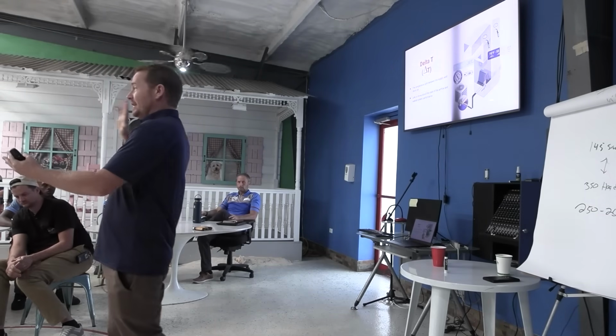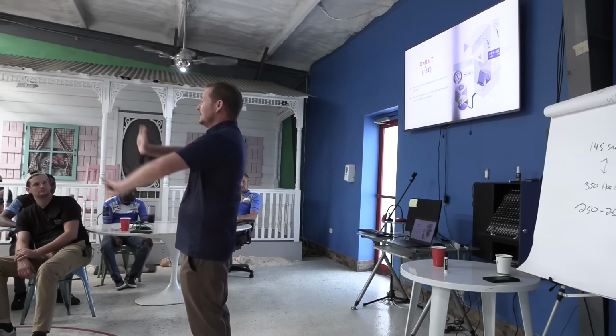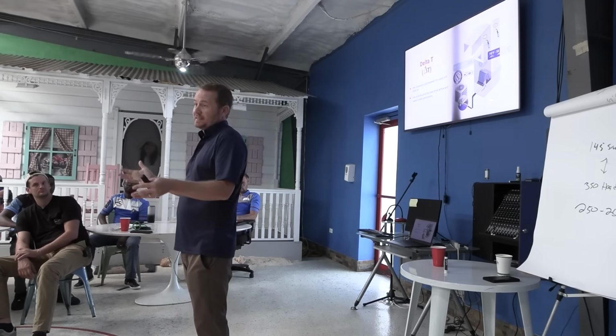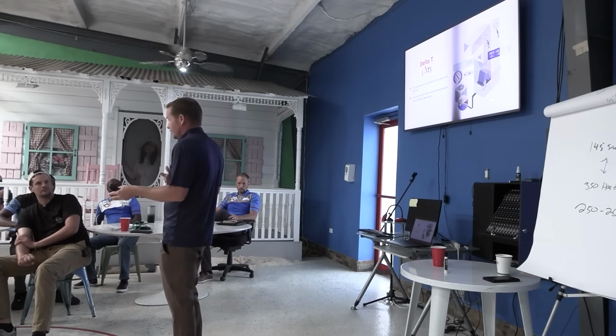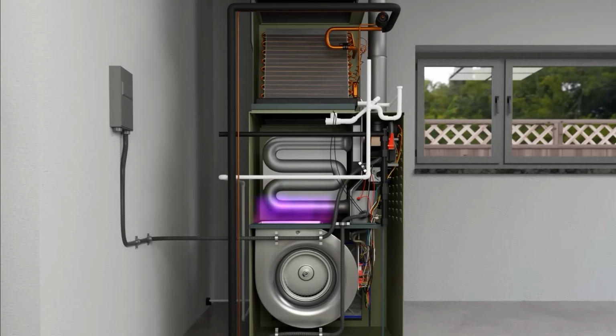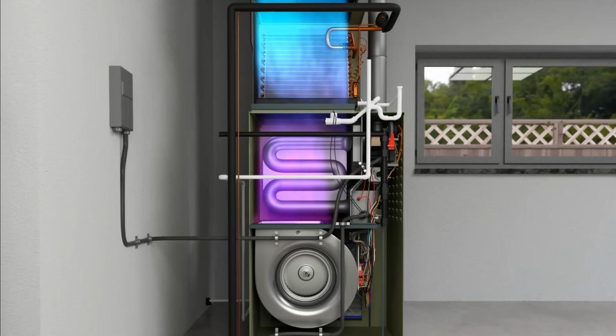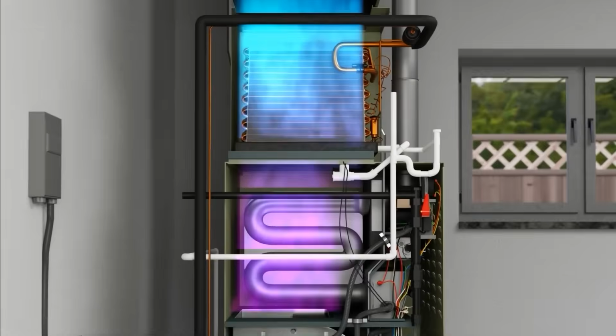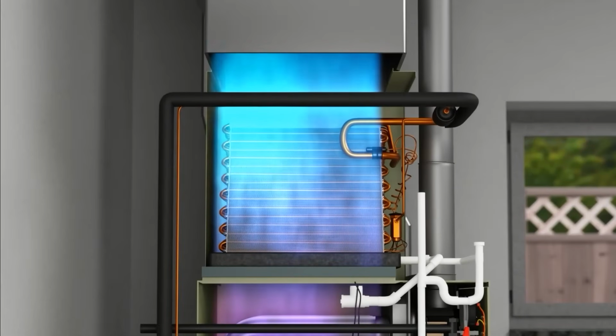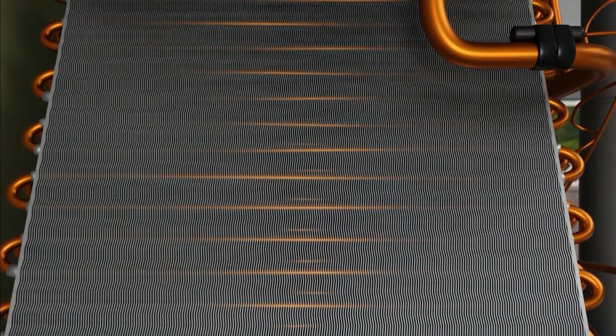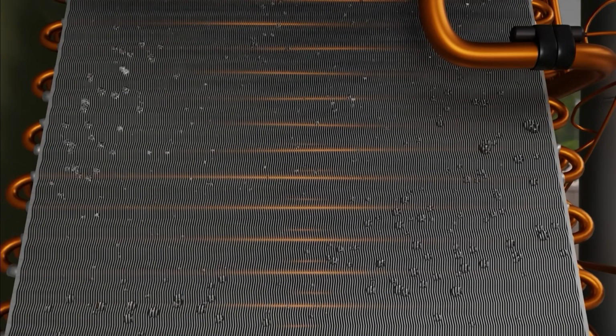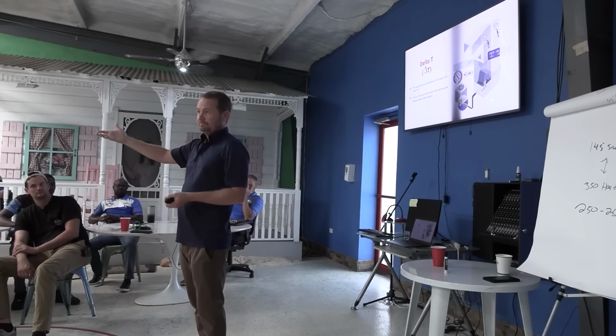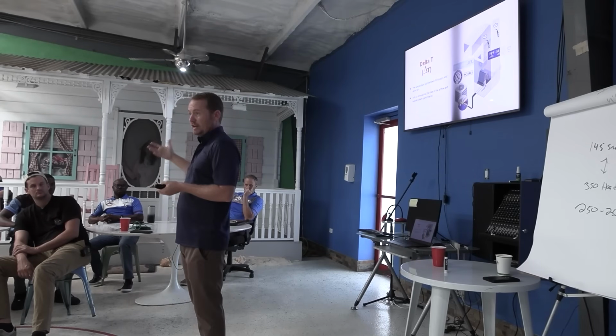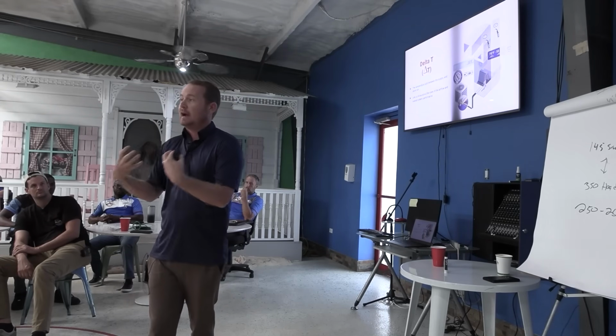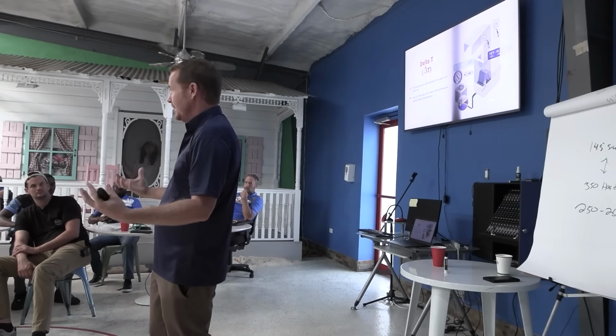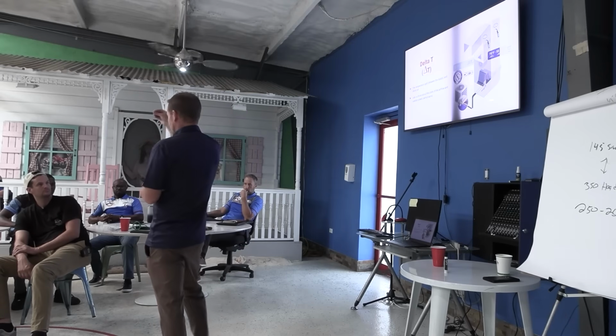But then there's latent of condensing water on your evaporator coil. Those are two completely different things. They're the same in the sense that you're changing things from vapor to liquid in both cases, but when you're condensing water on the outside of the evaporator coil, when it drains outside, it's because you changed it from vapor water to liquid water on that coil. The coil's below dew point, so it's condensing on that coil. That energy does not change the temperature of the air. It only goes toward that phase change, which means in markets like ours, a lot of the energy the air conditioner spends is being spent changing vapor water to liquid water.